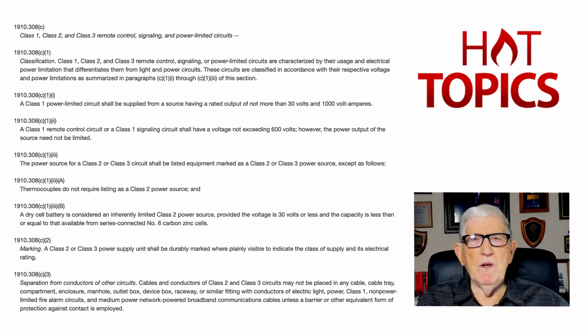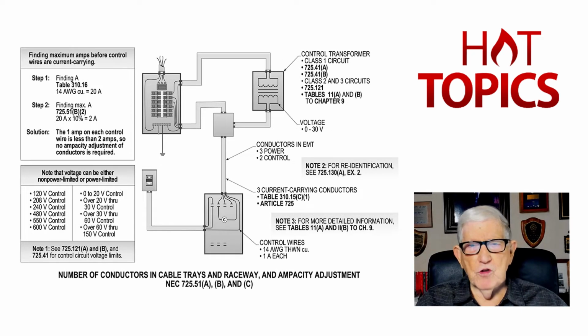Now, when we look at the illustration that's on your screen here, you notice that control circuitry, we're talking about on the secondary side of a control transformer maybe, or any type of class 2 circuit. Notice 725.41(a) deals with Class 1 circuits, as you see in the illustration, to the right, top hand side of the illustration. And they're power limited. And they are usually permissible to operate at 30 volts or less, and 1,000 volt amps or less. But usually you will find those operating at 30 volts or less, at 100 volt amps or less, is usually what you would find for that Class 1 circuit.